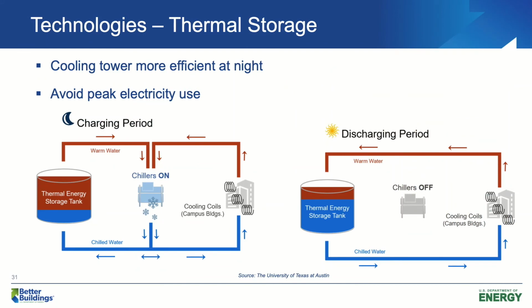Thermal storage. The idea of this technology is that at night, typically the outdoor air wet bulb temperature is lower, so our chillers will be more efficient. Typically, the demand charge is also low at night, so it will cost less to make chilled water at night. We will make a lot of chilled water or ice during the night when the outdoor air wet bulb temperature and demand charge are low, and we will turn off chillers during the day when the wet bulb temperature and demand charge are high. We will release the stored chilled water and ice to satisfy cooling loads and save energy cost. We would like to take advantage of the low wet bulb temperature and demand charge at night. That is the basic idea.